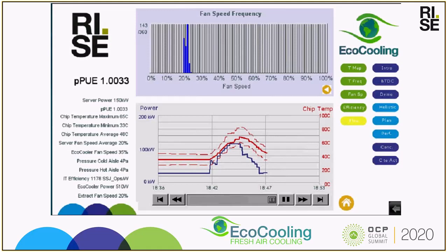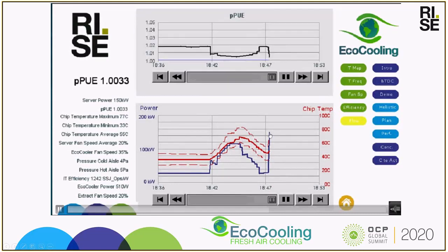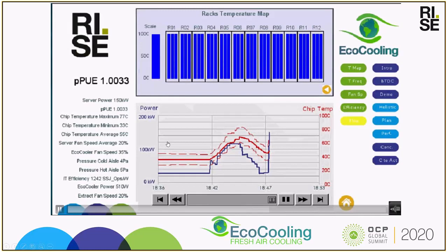So instantaneously, when we switch this on, the workload on all 360 servers simultaneously, we jump up to 150 kilowatts. Straight away, CPU temperatures start to increase rapidly, 55, 60 centigrade average, hottest at 77. And now we are stabilizing at around 140 kilowatts. There's a bit of a jump peak there.